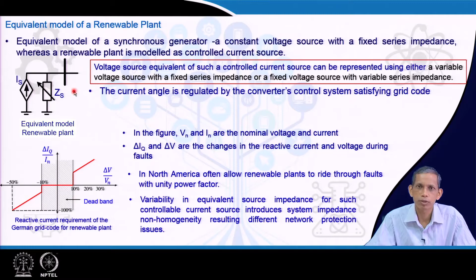So, these are the variations in the operational perspective of the converter during a fault: how the current injection happens, whether it is unity power factor or reactive power support. That makes the fault current with respect to the voltage at that bus different from the synchronous machine perspective. Variability in equivalent source impedance for such a controllable current source introduces system impedance non-homogeneity. The angle of the synchronous machine impedance and the angle of the transmission system impedance were considered to be of similar value in our earlier distance relay perspective, but here that does not hold because of these control operations. The equivalent impedance of the source varies significantly with time even during the fault, and so does the associated angle, which may not match the transmission system impedance angle.